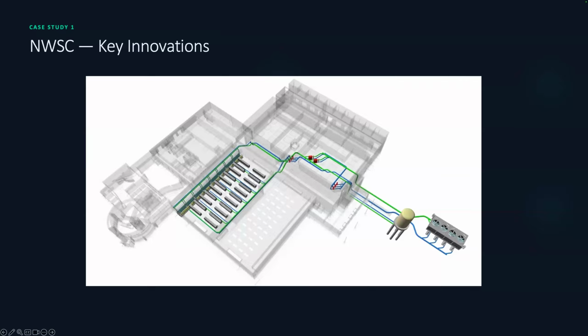So when you say thermal ride through, you just mean making sure the water is cool enough it can actually cool all the systems. You're not carrying heat through to the systems. Correct. So like the whole system's capacity to survive. Yep, exactly. Water was in the whole system versus the reservoir. The reservoir was about 2x the capacity of all the piping. And that was purely a function of how much ride-through time we wanted.